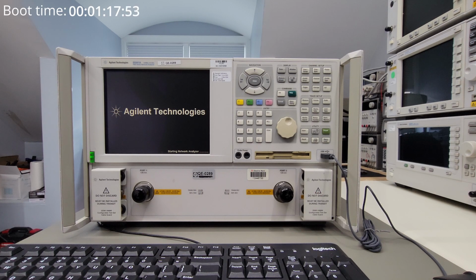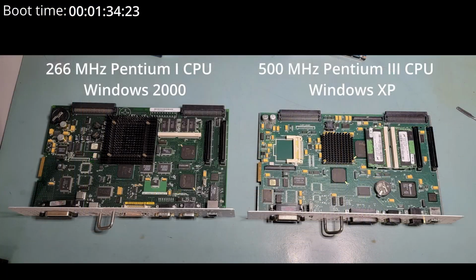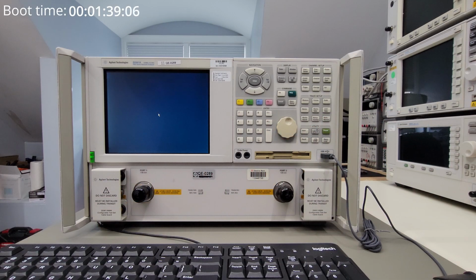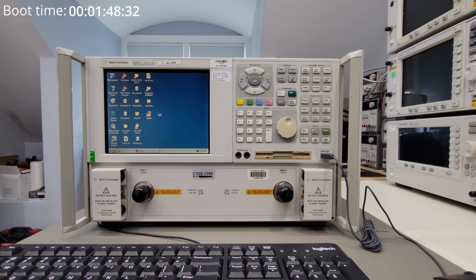Throughout the years, the processor and front panel were upgraded with A, B, and C revisions of each VNA model. In 2001, the first PNAs released ran Windows 2000 as an operating system. Later, the operating system was upgraded to Windows XP with the introduction of the 500 MHz Pentium 3 CPU board. The last of the legacy PNA series ran Windows XP with the 1100 MHz Pentium M processor and upgraded the storage to serial ATA. Now that the unit has finally booted, let's get into this repair.